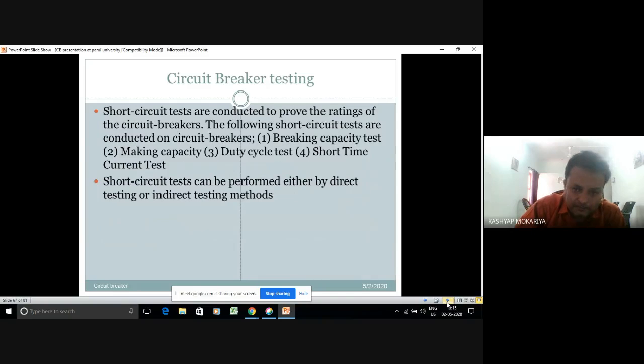Now, testing. Circuit breaker tests are conducted to prove the ratings of the circuit breaker. The following short circuit tests are conducted. Now see, don't mix up this circuit breaker testing with type test, routine test, development test, and commissioning test. They are a bunch of different tests. Now, at the manufacturer premises, you have to decide, because in a breaker the lethal fault is a three-phase dead short circuit, right?